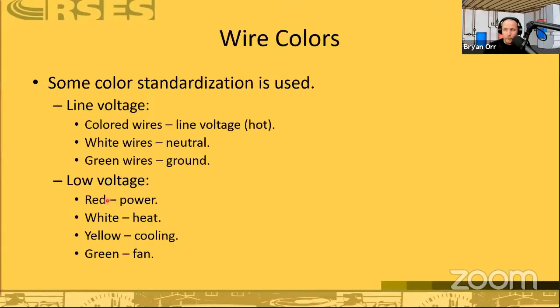Low voltage: red is 24 volt power. White is generally heat. Yellow is cooling on a straight cool unit, but on a heat pump yellow is actually the compressor contactor. The standard color code for the reversing valve is orange, unless it's a Rheem, then it's blue. Green is blower. Orange is a cooling call for the reversing valve, and blue is a heating call for the reversing valve. Rheem is one of the companies that uses that B terminal, which confused everybody.